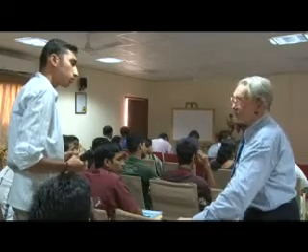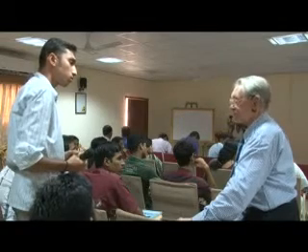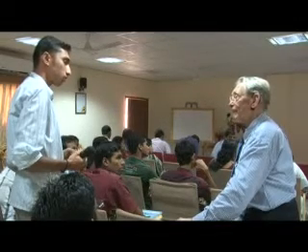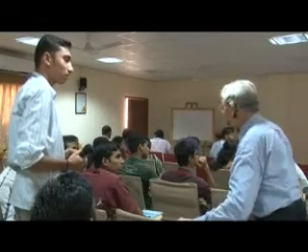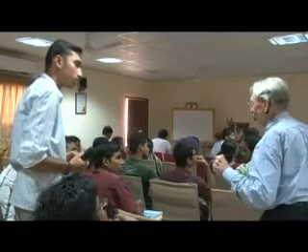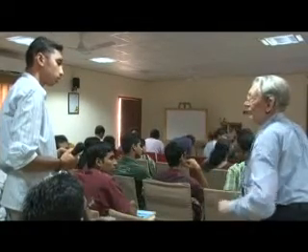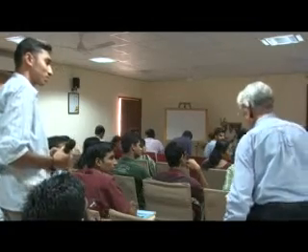Opening the wrong breaker is not unusual. Or closing the wrong breaker is not very unusual. It's a very valid and reasonable question, and it's a difficult one. I don't have a good answer. You suffer through it. And I guess my answer, if I were faced with it, my first inclination would be to close it, but don't do it. And my next inclination is wait until things are stable, and I know what I'm doing, and then bring the system up again. But management doesn't like that. They want the power.